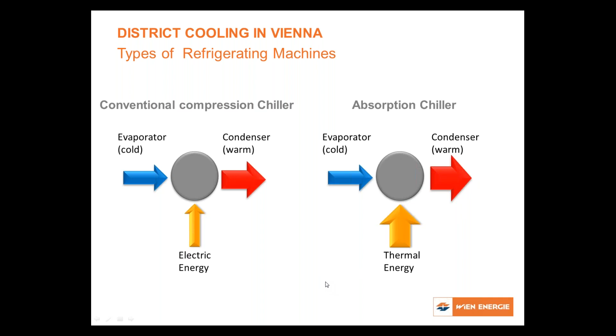When we talk about district cooling in Vienna, we offer our customers two different ways of cooling. One is district cooling, as you might know from district heating - there's a big plant, in this case a cooling plant, and via a district cooling network we supply our customers. The district cooling network is really small compared to the district heating network, at least in Vienna, so in terms of cherry picking to get even big customers, we also offer decentralized cooling: we build a small cooling plant, a chiller, at the customer's site, along with the recooling, so we can support the customer with cooling. In both cases, the customer gets the same service - cold power, cold energy in his building.